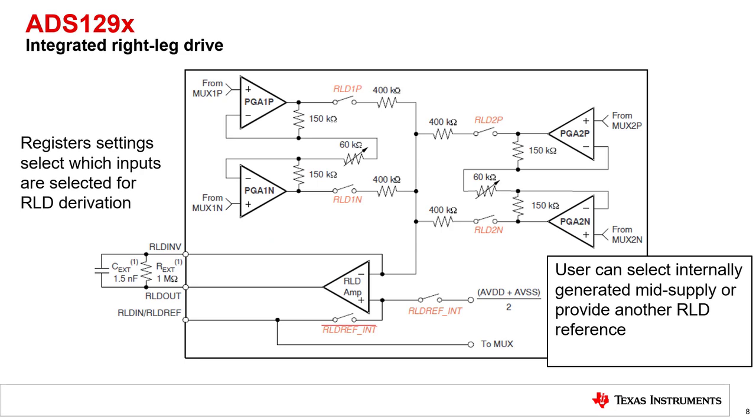The right leg drive amplifier and summing junction for the common mode voltage are also integrated with the ADS129X devices. This feature allows for some user programmability in order for the customer to design the best performance circuit depending on their application. An internal register selects which electrode inputs are allowed to feed to the RLD amplifier inverting input through the register summing junction. The output of the amplifier and feedback loop are connected to external device pins which allow the user to set the gain and bandwidth of the RLD circuit.